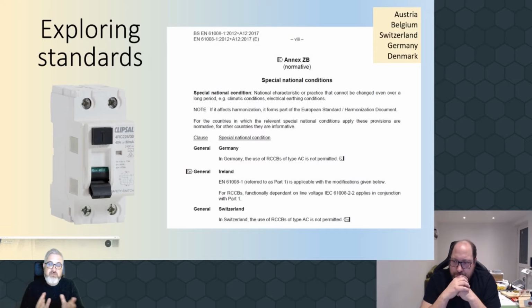Now, we're all very familiar with BS EN 60898 for MCBs. 61008 is the modern RCCB, replacing the old BS 4293. And if you combine the two, you get 61009. But this Annex ZB here is from 61008, so the modern RCD.